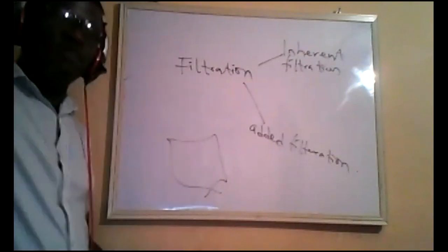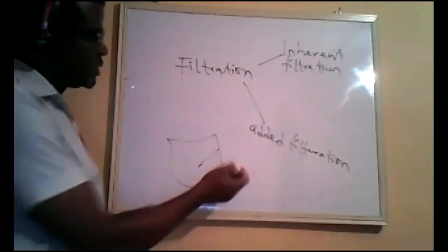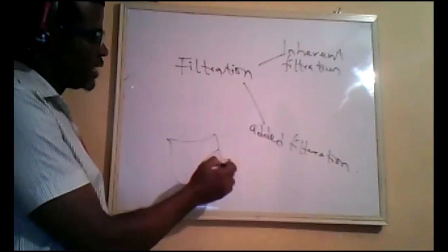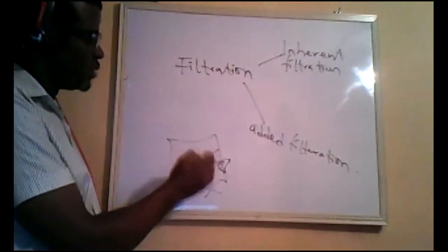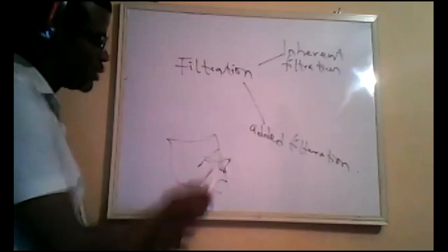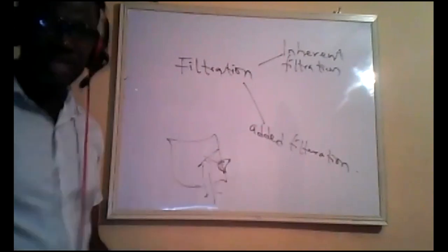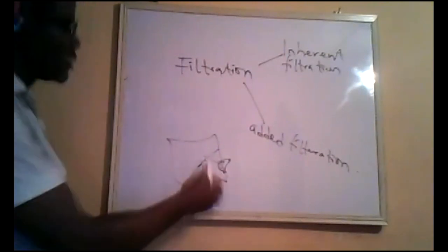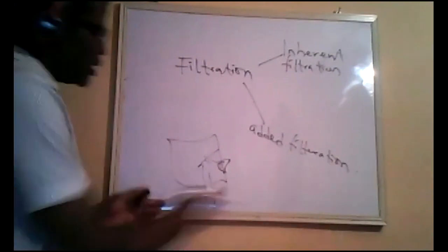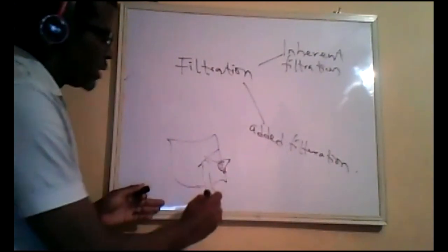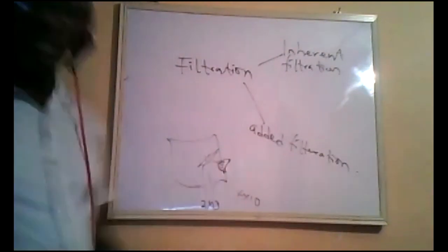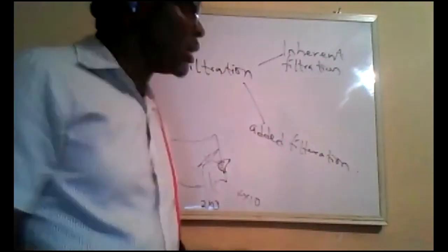Then we also have the mirror. There's a mirror inside the X-ray tube. We have a light source here. We put the light on, it strikes the mirror here, and it comes out through the collimator, through the port. This actually helps because we can't see photons, we can't see X-rays. So the light helps us to say, okay, this is the shape of the X-ray coming out, with the 2x3 or 4x10 and so on. So this mirror here also adds to the filtration of the X-ray.